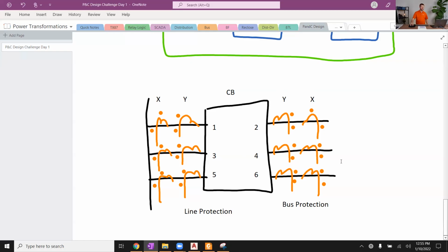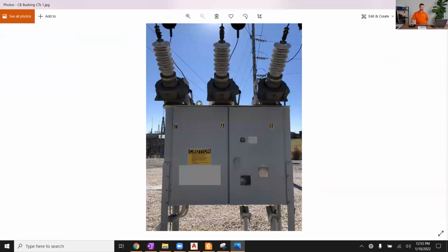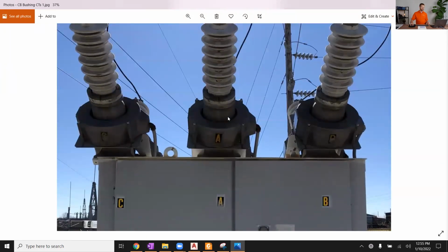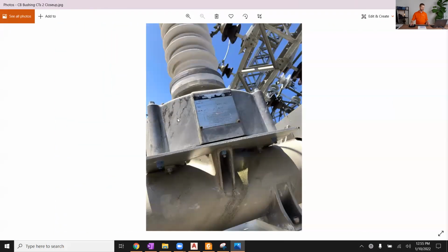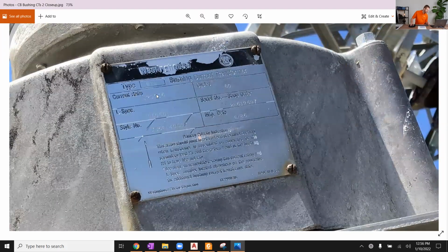Now, in case anybody's been confused by this, I have some pictures to show you, which might give a little more appreciation to what's going on here. This is an older breaker, 1980s style, and I think an old Westinghouse breaker. You can actually see up here on these breaker bushings, here's the bushing CTs. You can zoom in here, and here's a bushing CT from that same breaker. You see on the nameplate, bushing current transformer. Looks like it's a 1200:5 CT ratio here. It also has a notation about polarity indication, the polarity dot being the outer side of the bushing, like we were just sketching up there.